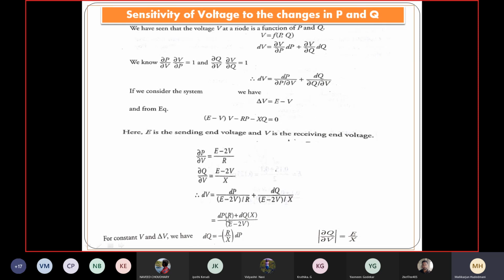I will be getting dP into R plus dQ into X divided by E − 2V, which stands as the small change in voltage dV. I am trying to bring in the sensitivity of voltage to reactive power. A small change in voltage dV is written as dP into R plus dQ into X over E − 2V. For a constant V, let's say the delivery voltage is constant and delta V is negligible. At that time, when dV goes to 0, I can surely write dP into R plus dQ into X divided by E − 2V.